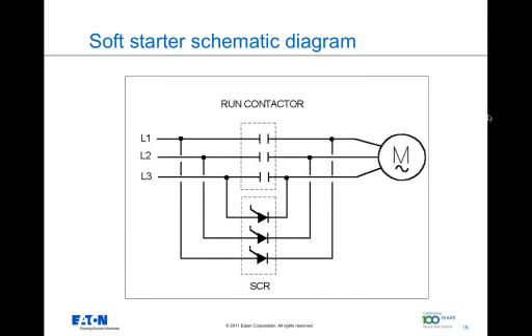Whenever a system is run with the SCRs, a huge amount of heat is generated, but soon after its purpose is done, the system can go into the run bypass contactor, which is a mechanical contactor, and that significantly reduces the heat generated in the system.